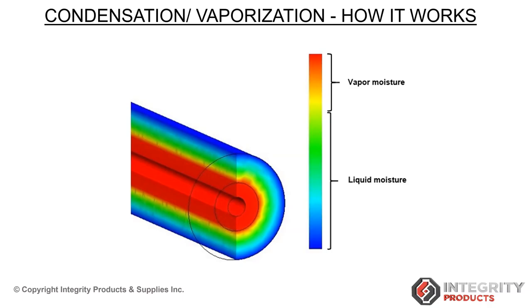Absolutely. And it is complete clear evidence that the insulation that was soaking wet at around 80% moisture was almost dry in June. Yeah, for sure. And I know our study stretched from October 2019 till June 2020, but in our initial 4 to 6 weeks of the testing period, we've seen on many of the lines that we were testing the moisture content go from above 80% down to below 5% in a 4 to 6 week period. Again, the benefit of doing it in Alberta during the wintertime was we were able to see the sheer volume of moisture which was allowed to exit the system, because we're now giving it the room and the means to drain and pool to the 6 o'clock position and then leave the system through our drains. So yeah, absolutely.